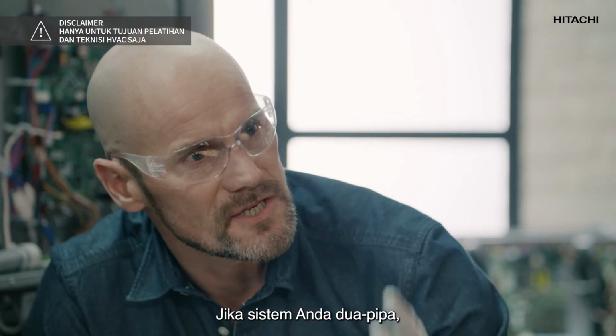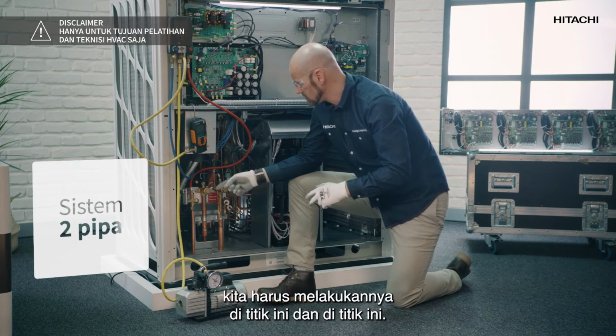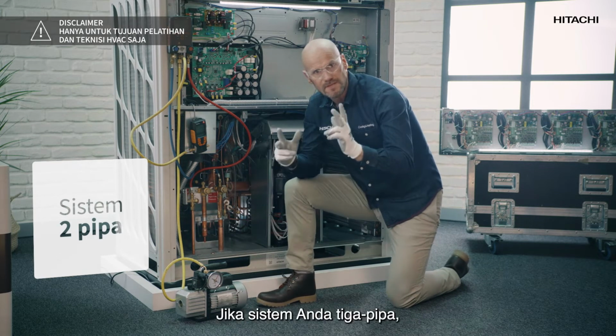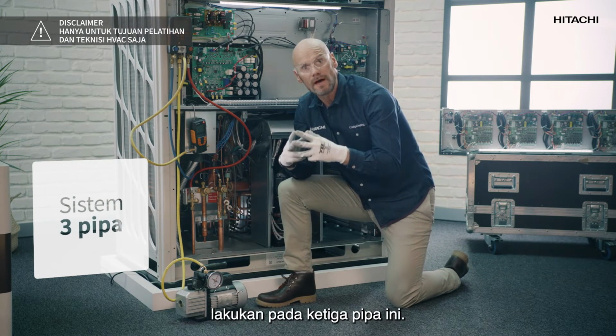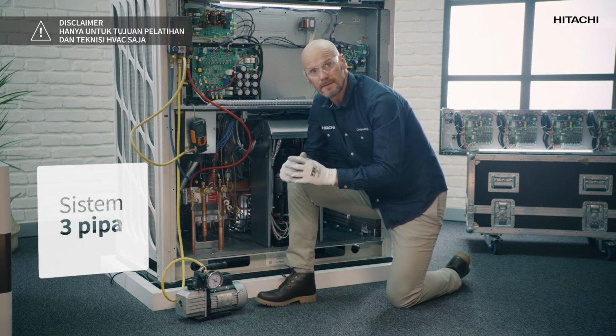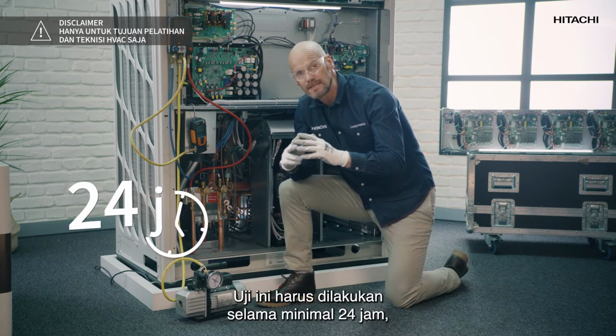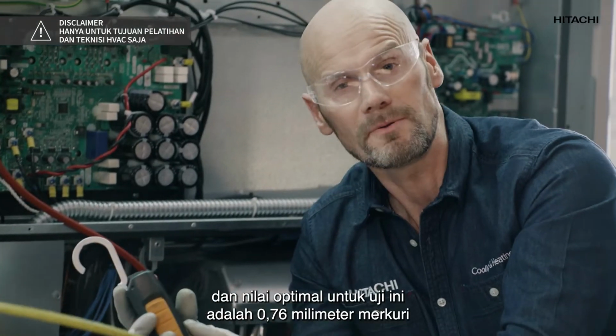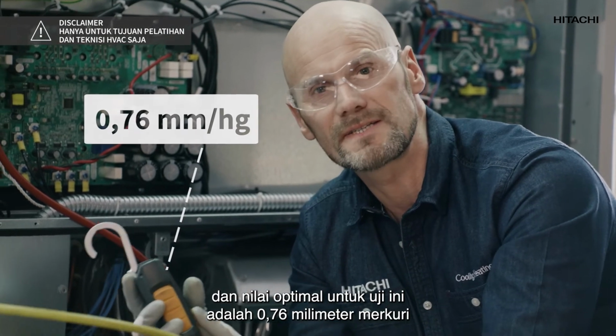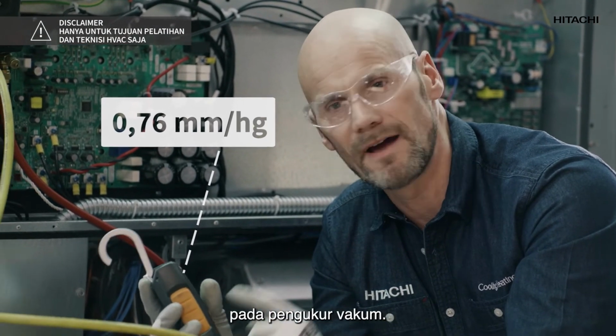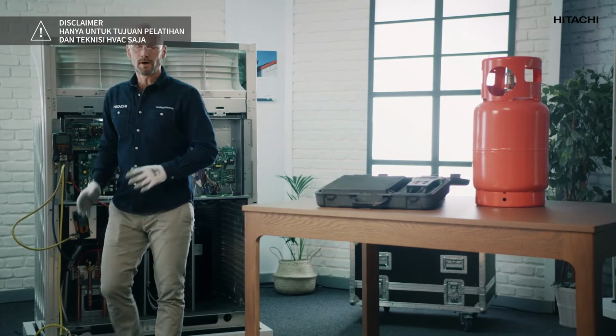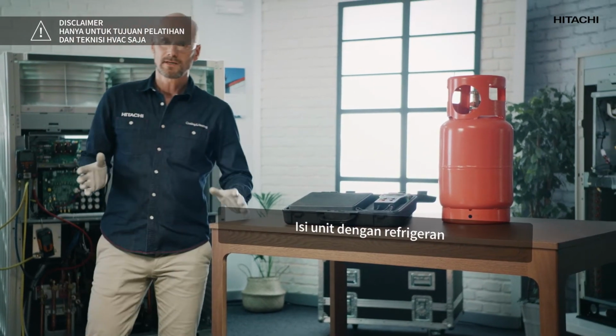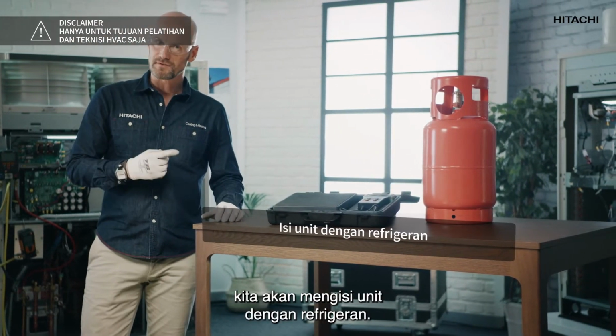If your system is a 2-pipe system, we have to do it at this point and at this point. If your system is a 3-pipe system, you have to do it for these 3 pipes. This test must be run for at least 24 hours. And the optimal value for this test will be 0.76 mm mercury on the vacuum gauge. Once we have checked that the vacuum is satisfactory, we will charge the unit with refrigerant.